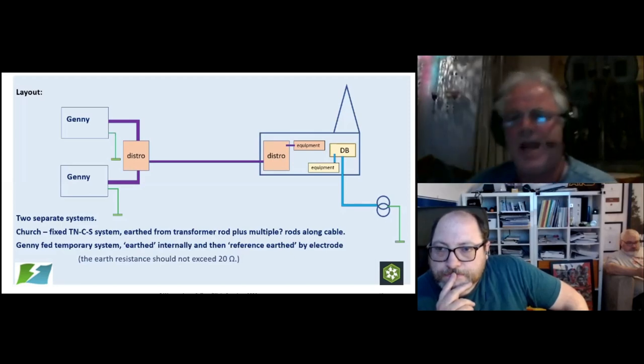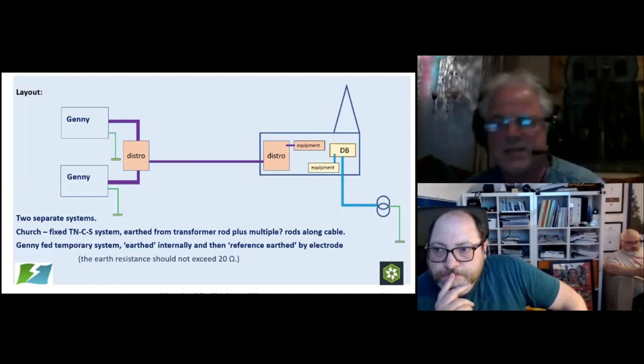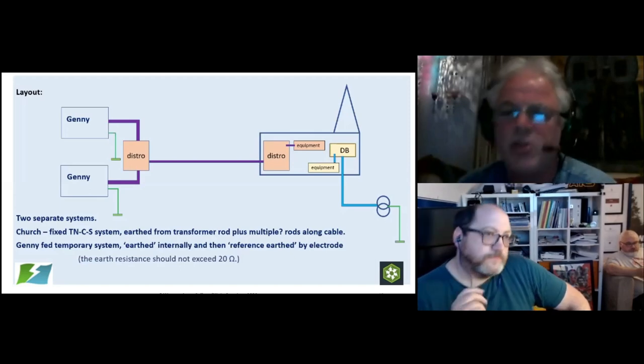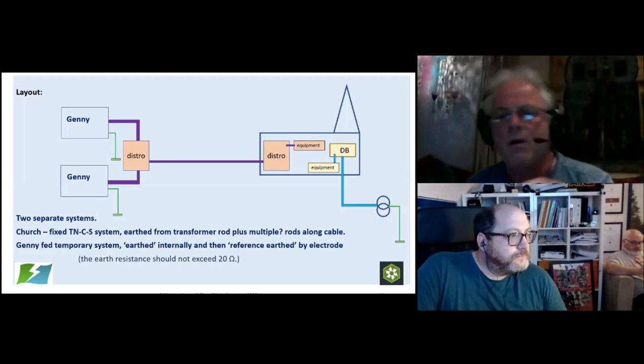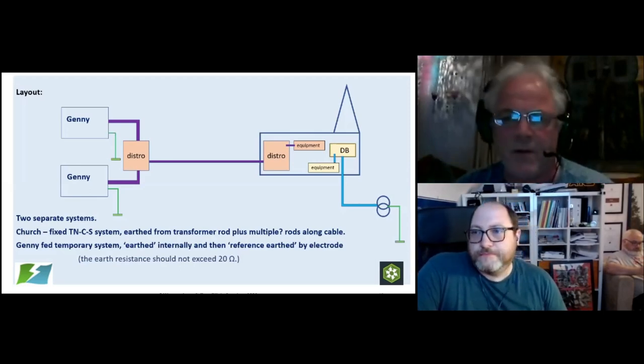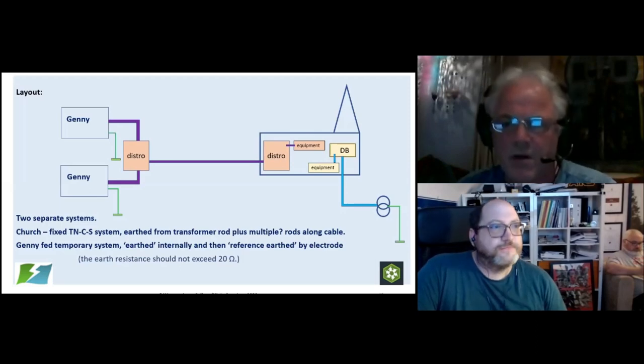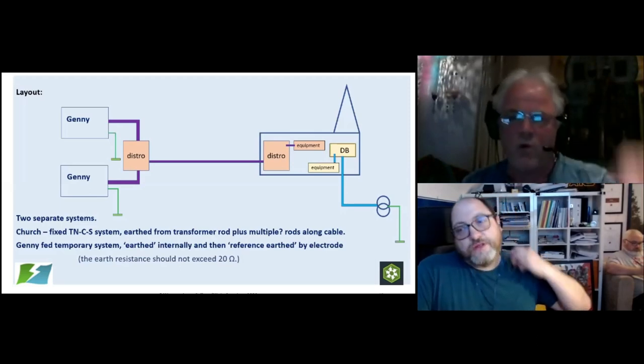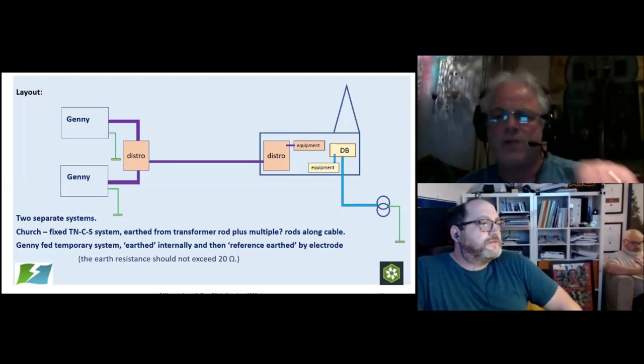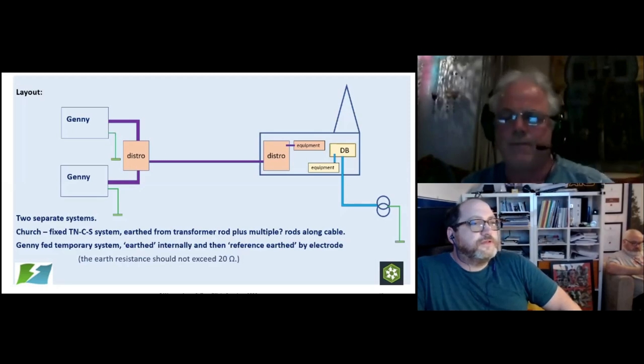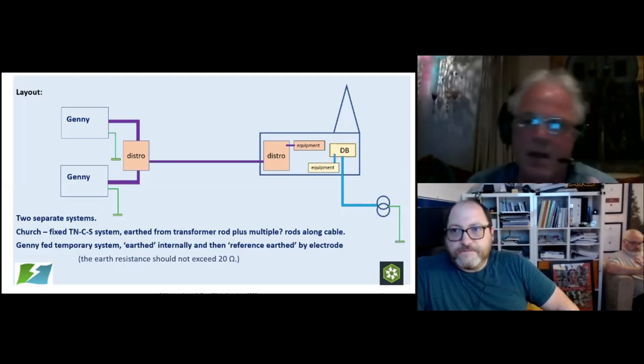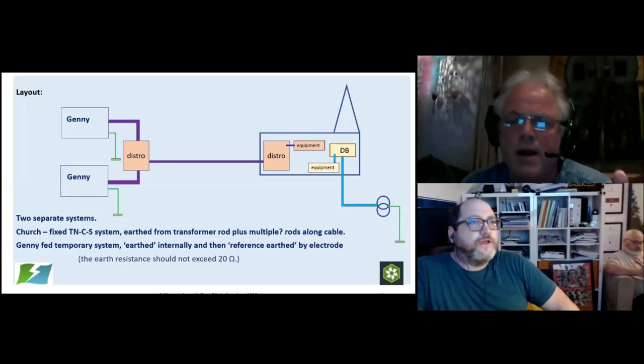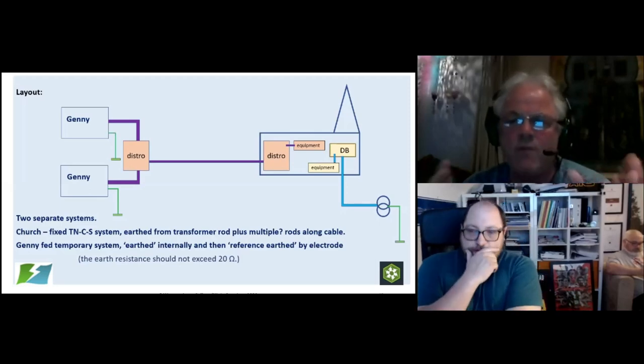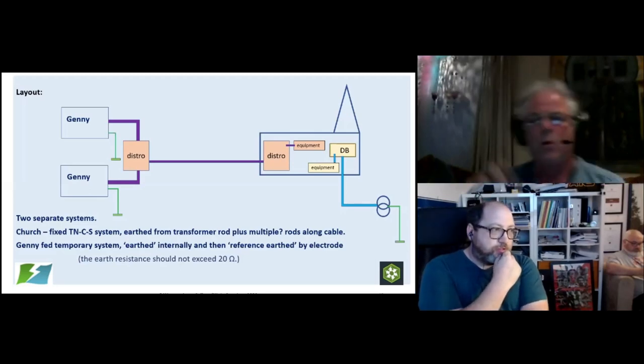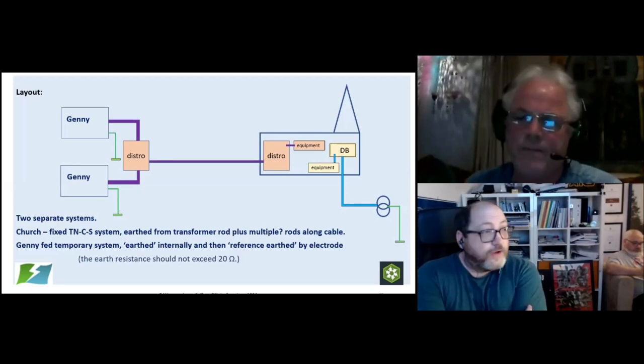So you have the option with a fixed installation earth electrode of testing it either using an earth electrode resistance tester or using an earth loop impedance tester, because you have a fixed system with a return path. Within a generator, you can't test it using an earth loop impedance tester because there is no path, there is no circle. You're looking at just a single rod in the ground. And when you're testing the earth electrode resistance, you are testing the resistance of the ground. So when we're looking at this 20 ohm value, there's no reason at all why you can't achieve that with an earth electrode resistance test. Remember, it's a different test to when we're testing a fixed installation earth electrode. A totally different test.